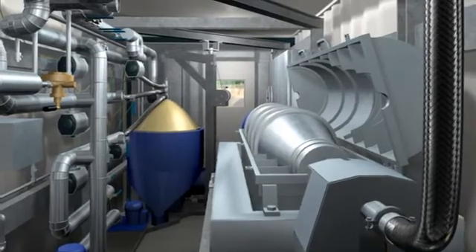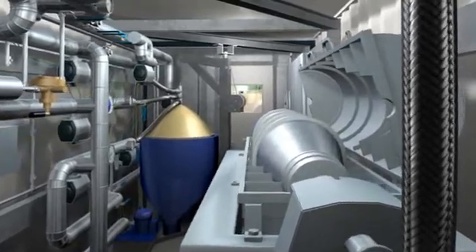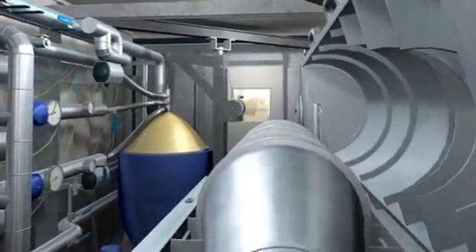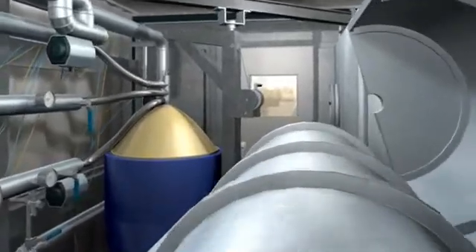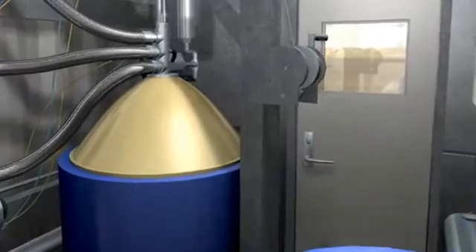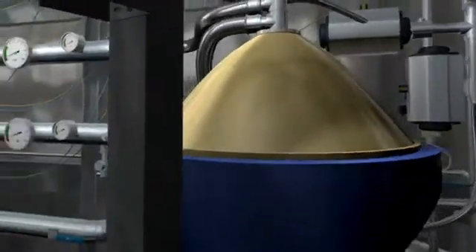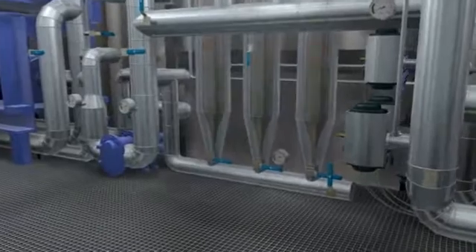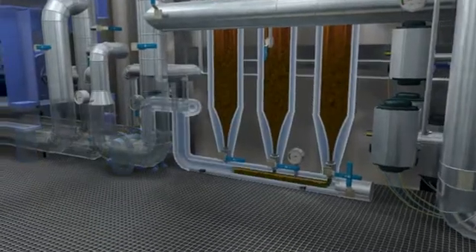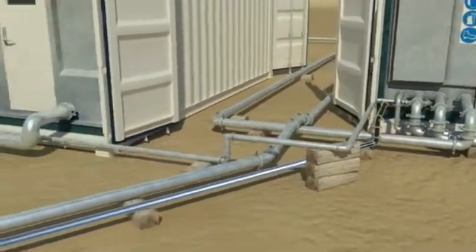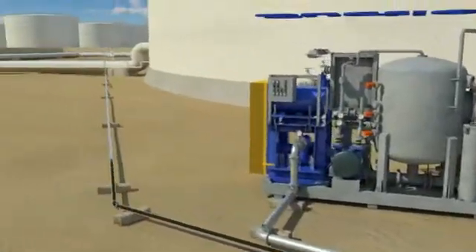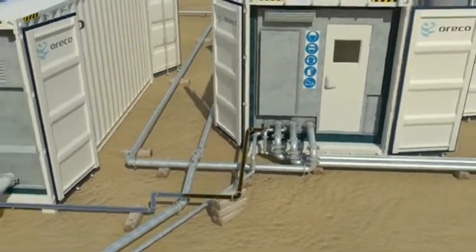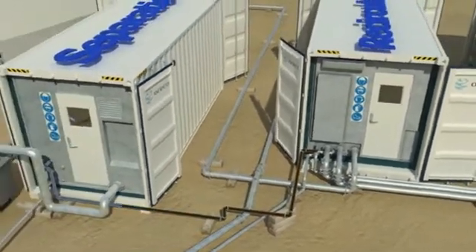The separation process takes place simultaneously with desludging. The separation module enables tank owners to achieve specific separation requirements. One can opt to run a liquid-solid separation only using the decanter or to perform a further oil-water separation of the liquid via the high-speed separator. If the oil fraction at the bottom of the hydrocyclones matches the tank owner's specifications, the oil is pumped directly to the pipeline.